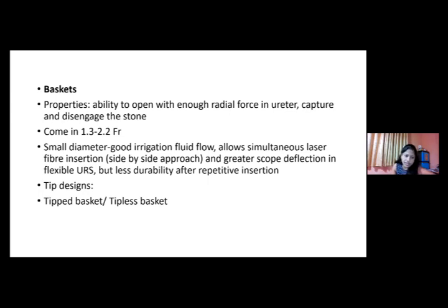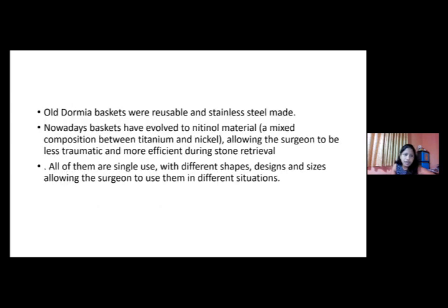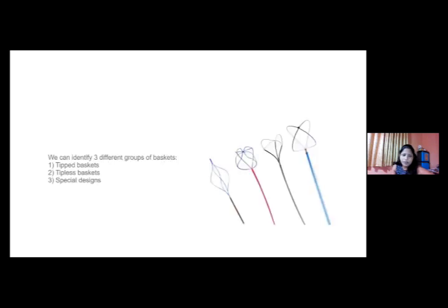We have various designs. It can be tipped or tipless. The old baskets were reusable and made of stainless steel, but nowadays baskets are made of nitinol material. Nitinol is a mixed composition of titanium and nickel, which allows the surgeon to be less traumatic and more efficient during stone retrieval. All of them are single use, but come in different shapes and designs. In the market we have tip baskets, tipless baskets, and baskets with special designs.